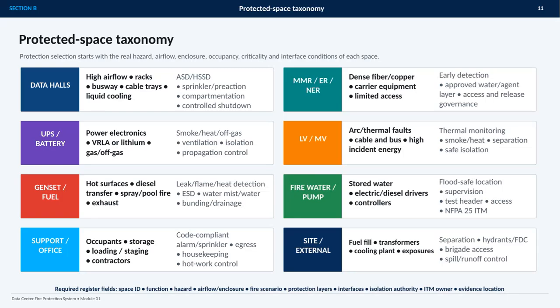This slide establishes a protected space taxonomy for selecting fire protection based on the actual conditions in each space, rather than applying one solution everywhere. The assessment should consider the hazard, airflow, enclosure, occupancy, criticality, and interface conditions. Data halls require attention to high airflow, racks, busways, cable trays, and liquid cooling, with layers such as early detection, sprinklers or preaction, compartmentation, and controlled shutdown. MMR, ER, and NER spaces add dense fiber and carrier equipment, so detection, approved suppression, and access governance become especially important. UPS and battery rooms introduce power electronics, battery gases, ventilation, isolation, and propagation control. Electrical rooms, generators, fuel systems, fire water infrastructure, support areas, and external site hazards each have different scenarios and controls, from arc faults and hot surfaces to fuel spills, pump reliability, egress, and brigade access.